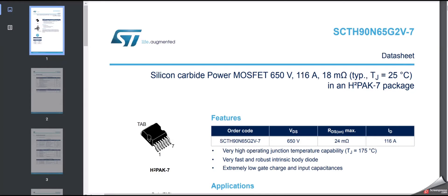The gate driver IC supplies, let's say, 10 or 12 volts depending on the application. The main concern is that the MOSFET should not turn on unintentionally when it is not required. If the MOSFET does unintentionally turn on, it can lead to linear mode operation, MOSFET failure, and ultimately a fire event in your converter.